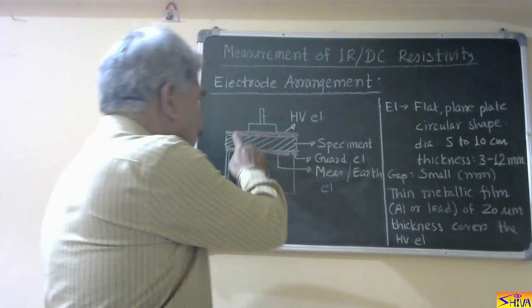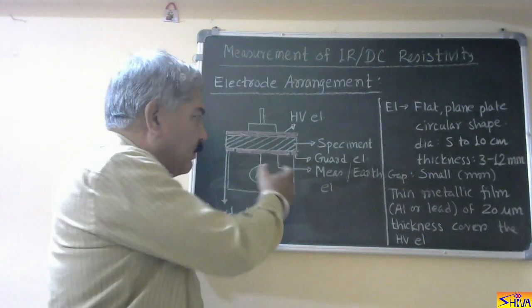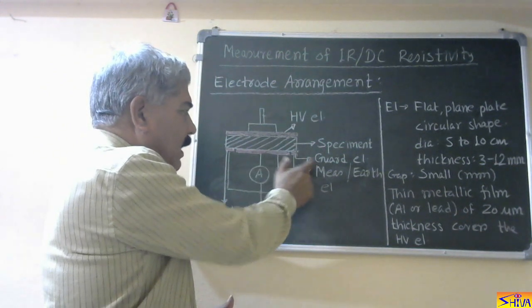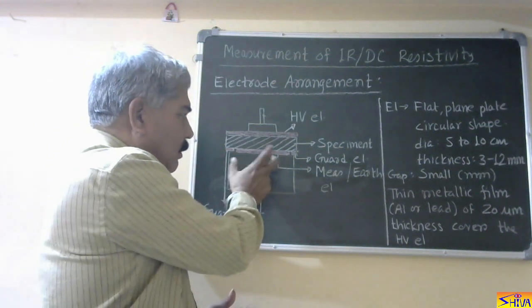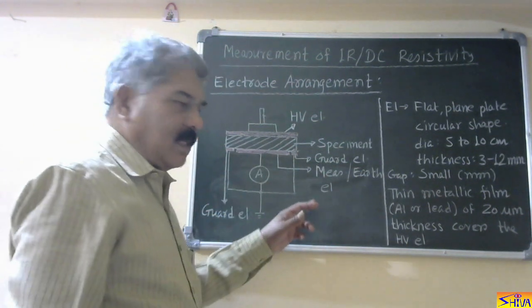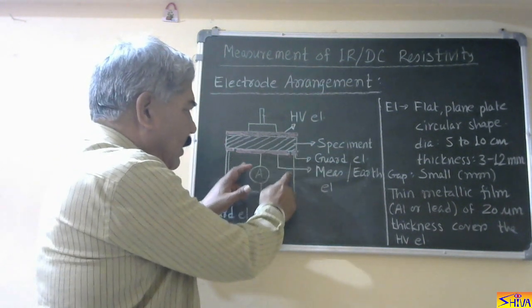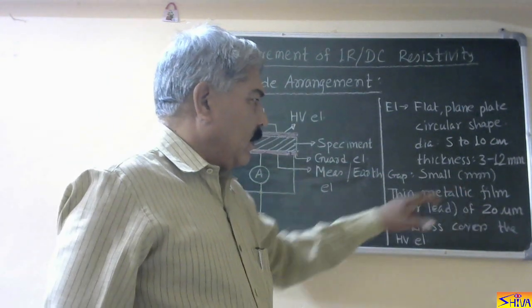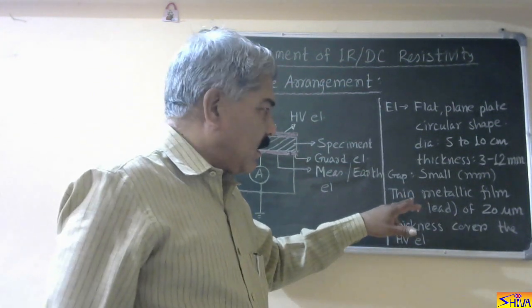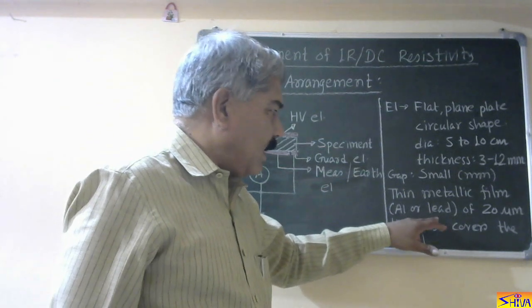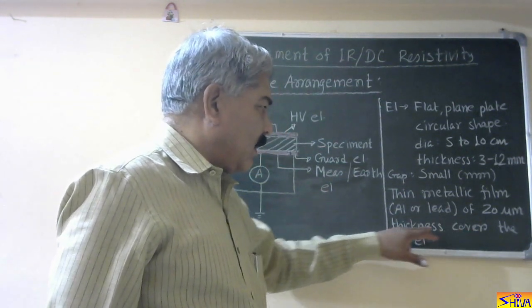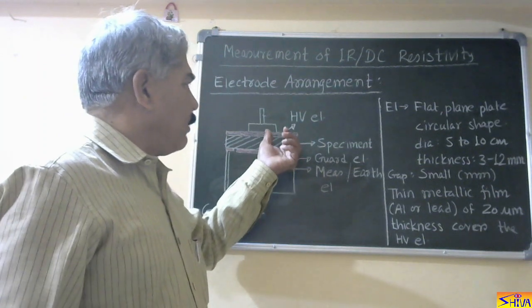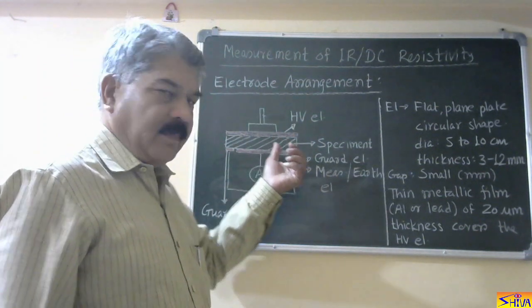There is an upper circular electrode. Below this is the specimen, which is also circular. Then there is an outer ring, called the guard electrode, and an inner flat measuring electrode also called the earth electrode. The gap between the guard electrode and earth electrode is very small, in the range of a few mm. A thin metallic film of aluminum or lead of 20 micrometer thickness covers the high voltage electrode to make better contact between the high voltage electrode and the specimen.